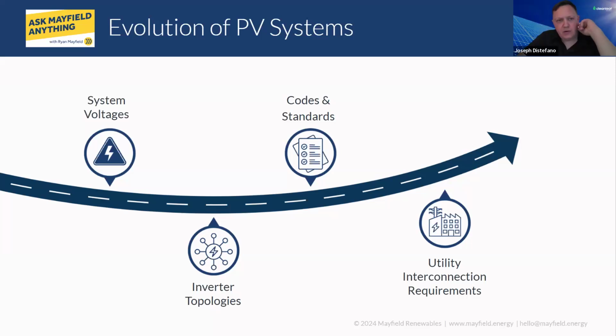It all depends on the scenario. Typically in a rooftop application, we trigger new NEC requirements for rapid shutdown, so we already assume we'll have to do some restringing, especially for the old 600-volt legacy projects. On some of the newer 1,000-volt rated systems, we'd love to save the combiner boxes and DC string wiring infrastructure and just focus on the equipment.